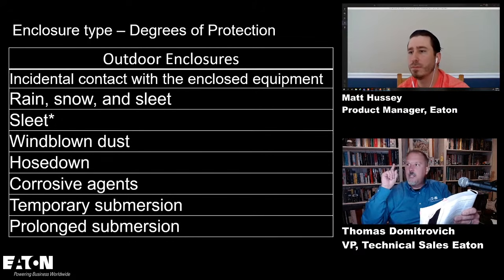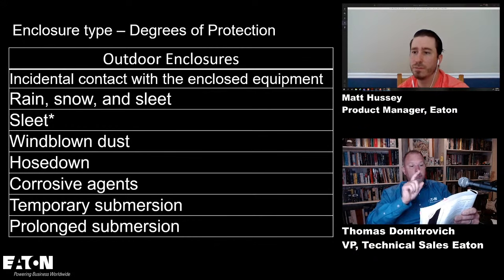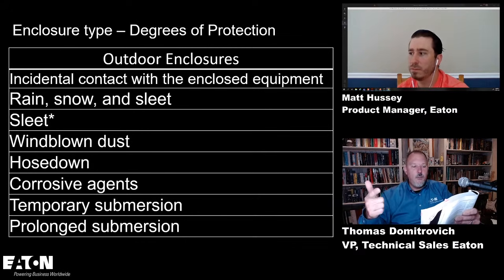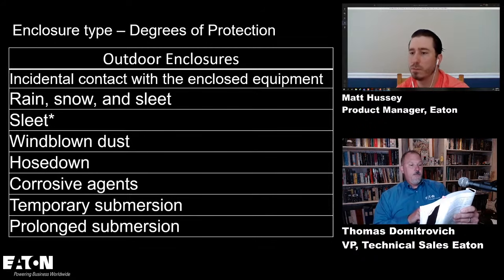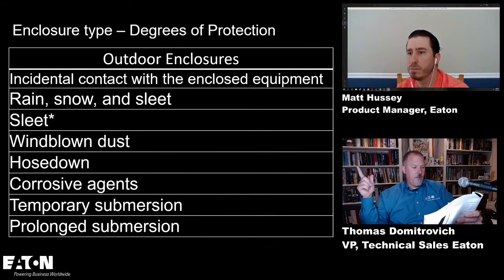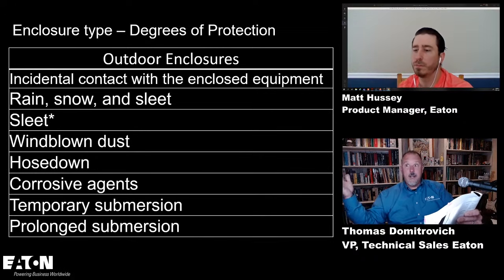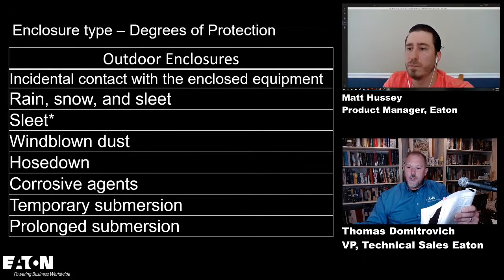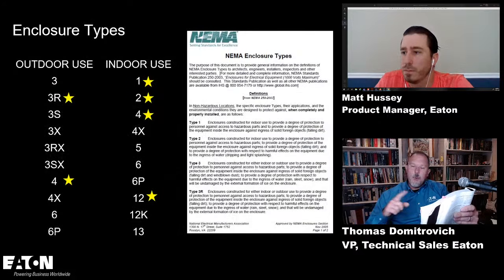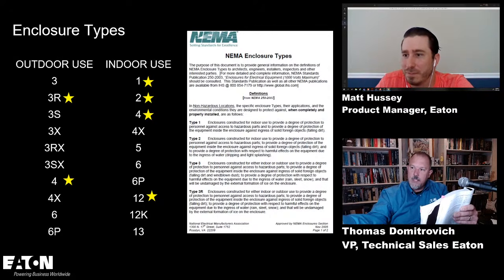So I'm going to go one more. Outdoor enclosures, right? So this is the 3R, and everything listed in that area. So 3R, 3S, 3X, all of those, and the 4s, they all give you incidental contact. They give you rain, snow, and sleet. Only the 3S and 3SX give you the sleet, actually, with a star. I don't know what the star means. Mechanical mechanism shall be operable when ice covered. So in any case, what I found interesting was, where's it at? And Matt pointed this out. I have indoor use 1, 2, 4, 4X, 5, 6, 6P, 12, 12K, and 13. Outdoor use, I have the 3s and the 4s and the 6s.